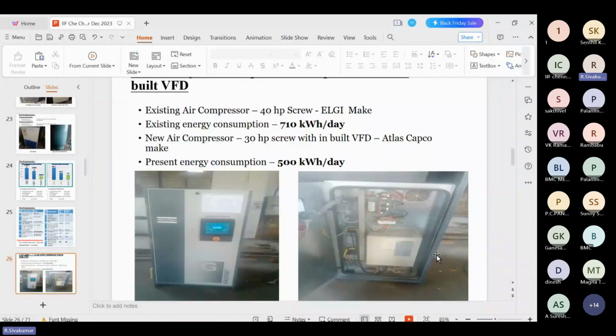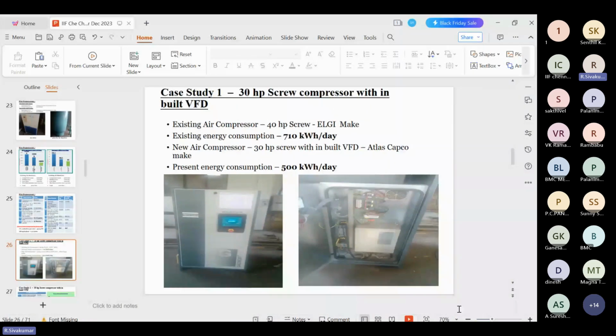The other case study is, during our energy study, we suggested replacing a screw compressor with VFD. The existing one is a 40 HP screw compressor. It was replaced with a 30 HP screw compressor with inbuilt VFD, because the old compressor is almost 15 years old and its efficiency is very low. That's why we suggested it. After this, the unit consumption is only 500. Nearly 210 units were saved with the new air compressor.